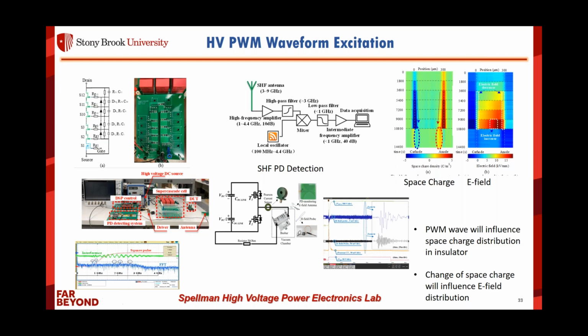If we're doing this test in switch mode or PWM operation, it's really hard to detect the PD event because there are two parts of current. The first is the displacement current. If your insulator is right here, you can consider it a capacitor, so you always have charging and discharging current going through it as you shoot square pulses across the DUT. This displacement current will get mixed with your partial discharge current, and if you're only using a Pearson probe or Coulomb meter to gauge space charge, you won't be able to separate them.